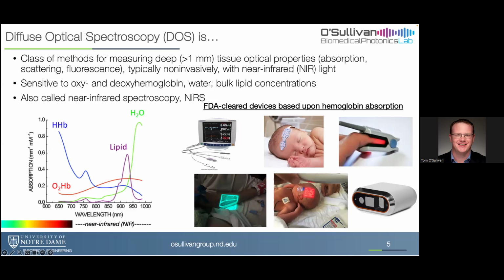So CW brain cerebral oximeters typically use 4 wavelengths. They've got one right around 706. Good. What else? The 950, right? It's like 940 to 980. Yeah, water peaks over hemoglobin, where you get some attenuation there. Yep.